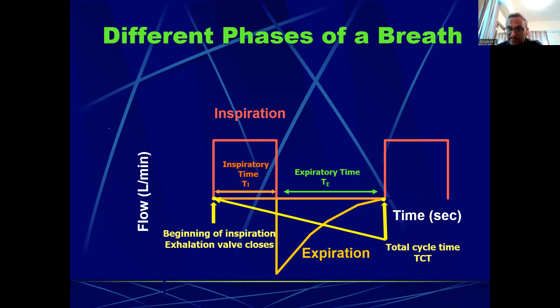And once the exhalation valve closes, depending on whether it is volume or pressure, here we are talking about volume ventilation, so I'll stick to that, you set a certain volume or pressure, and the machine gives a certain flow to reach that tidal volume, depending on what inspiratory time you have given. As I told you, volume is flow multiplied by time. Or if it is pressure ventilation, the flow is created in such a way that a certain pressure is reached. So this is where the peak inspiratory flow rate happens, determined by what you have set, whether tidal volume or pressure.